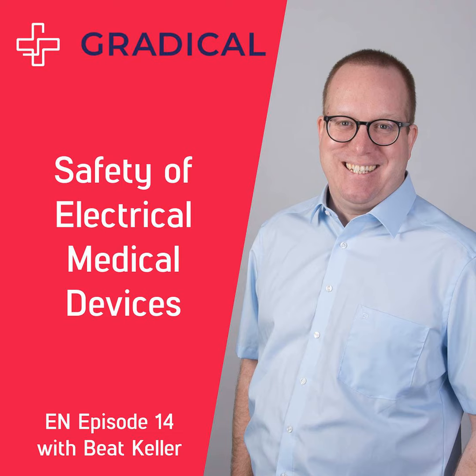Yeah. So there's a complete section in the 60601 about mechanical strengths. And especially if you're then going to home healthcare or emergency healthcare, which is even worse, then you have much higher mechanical strength tests you need to perform. The worst I've ever seen is emergency care devices for helicopters. If you're an engineer and see your device on a shaker on a helicopter performing tests, then your heart will start bleeding, seeing what you can do with a device on such a shaker.